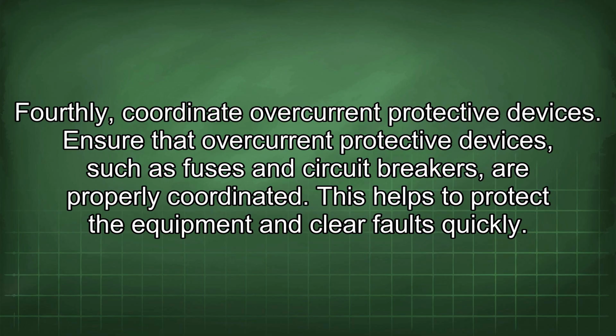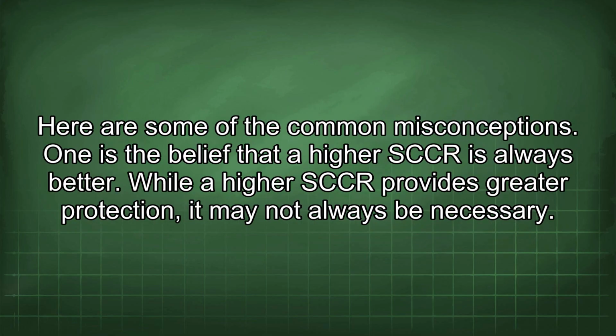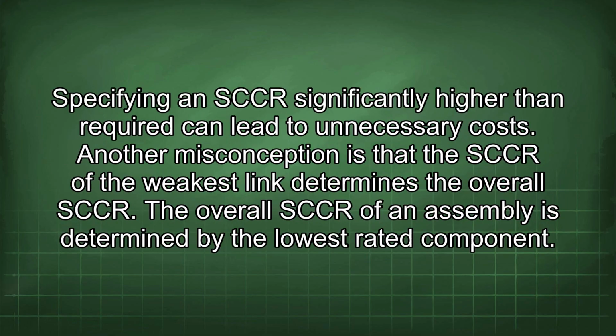Fourthly, coordinate overcurrent protective devices. Ensure that overcurrent protective devices, such as fuses and circuit breakers, are properly coordinated. This helps to protect the equipment and clear faults quickly. Here are some of the common misconceptions. One is the belief that a higher SCCR is always better. While higher SCCR provides greater protection, it may not always be necessary. Specifying an SCCR significantly higher than required can lead to unnecessary costs.